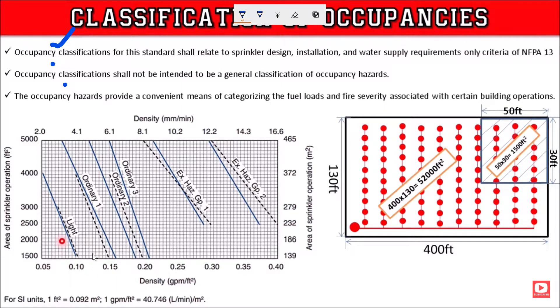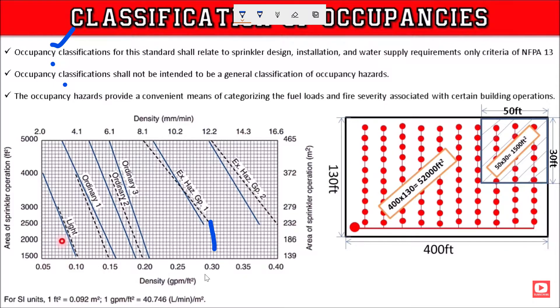The design density is given in GPM per square foot. For light hazard, the density is 0.1 GPM per square foot. For ordinary hazard, the density is 0.2 GPM per square foot. For extra hazard group, the density is 0.3 GPM per square foot. These are the standard American values as per NFPA 13.